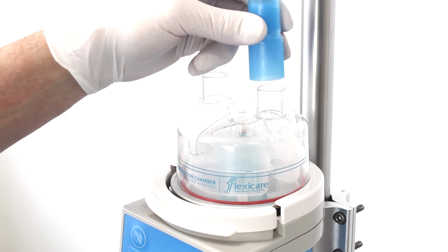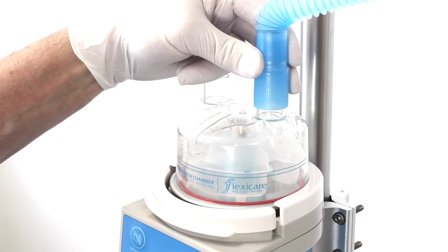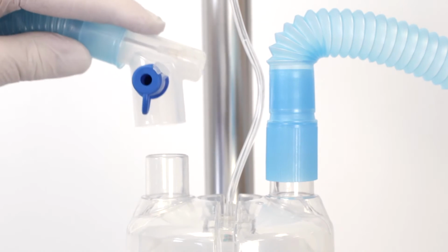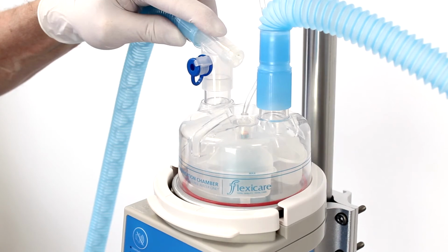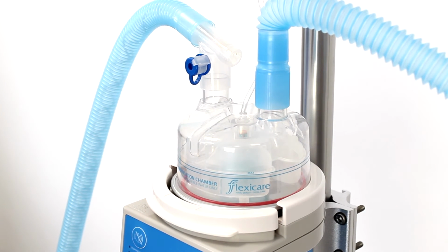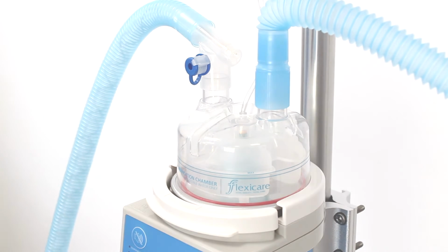Attach the blue ventilator limb to one chamber port and to the ventilator. Connect the inspiratory limb to the other port of the chamber. Please note that either chamber port can be used as the inspiratory or ventilator connection.